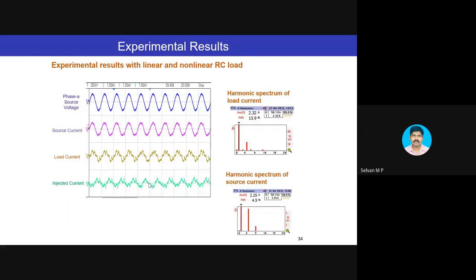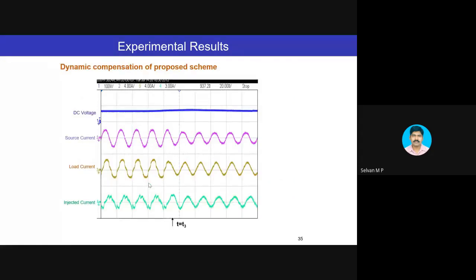Similarly, an RC load, nonlinear RC load, and the dynamic compensation. See, dynamic compensation means you can see here the load current is changing, right? The load current magnitude is changing. That is the dynamic compensation. The load current magnitude is changing, as well as suddenly it is changing. Whether the voltage source converter is capable of giving reactive power for this sudden change. Yes, of course, it is capable of responding. Within half cycle, it is responding and it is making the wave shape pure sine.